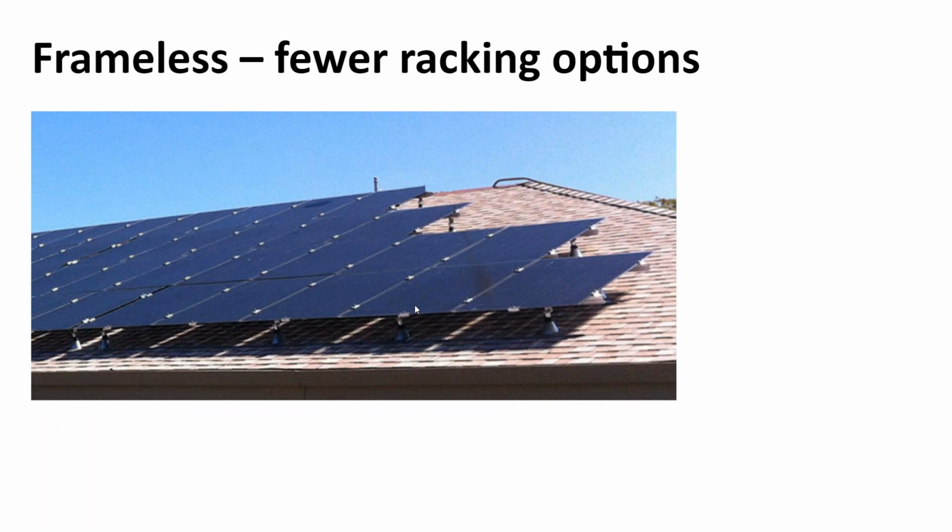At any rate, some interesting things about a frameless solar panel, when we talk about panel degradation in a minute: there's less metal, and metal on a roof has to be grounded. So metal module frames are grounded into the racking. And you can get some electrons leaking out of the system, not in any perceptible or measurable way. We're talking about electrons, not enough to generate a discernible current, that might leak from the cells into the metal and then out the grounding system, never to return.